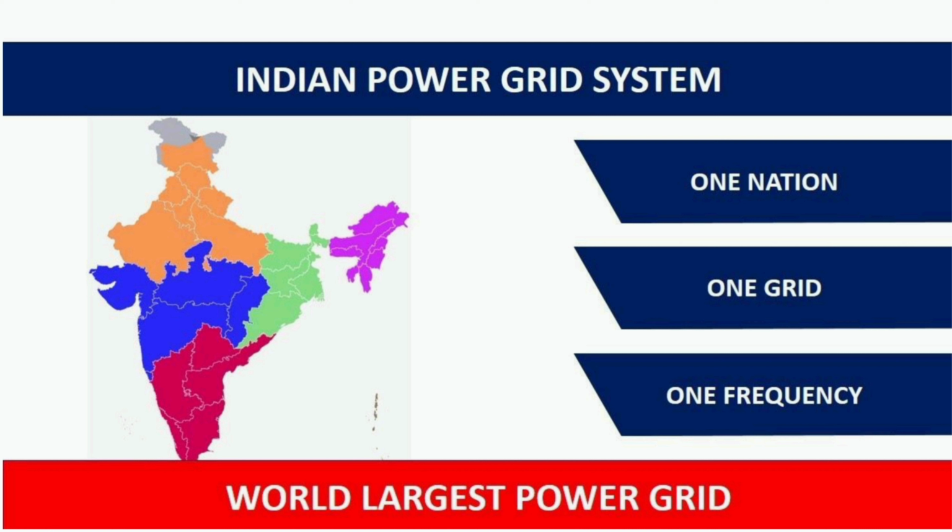All possible measures are taken to ensure that the grid frequency always remains within the 49.90 to 50.05 Hz band. Maintaining a constant electrical frequency is important because multiple frequencies cannot operate alongside each other without damaging equipment. This has serious implications when providing electricity at a national scale.